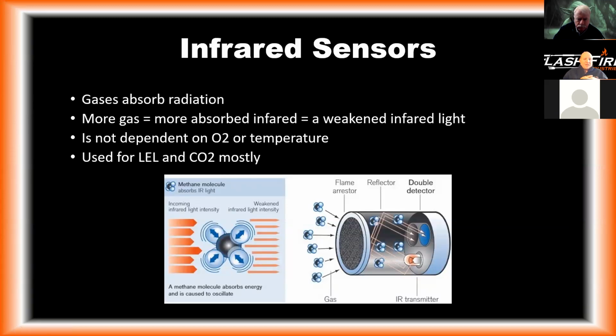The infrared sensors, this is not a sensor that you guys have in your arsenal, but it's just good to know that it's out there. It absorbs gas based on the radiation, and more gas, more absorbed infrared energy, the weakened light, and that's what gives you your reading. Two times this sensor gets used a lot is for LEL and CO2, carbon dioxide. What's nice about it is it's not affected by oxygen or temperature.